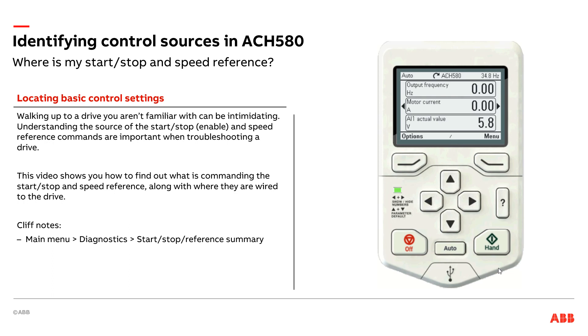So taking a quick step back, why would I care about how to find my start/stop and my speed reference? When you're trying to do that troubleshooting and you're walking up to a drive for the first time — you're not the one who configured it, you didn't program it, you didn't commission it — but you want to know about that drive because you've got to solve the challenge. First thing I like to know is where my start/stop landed, what's controlling the speed, and where that speed signal landed.